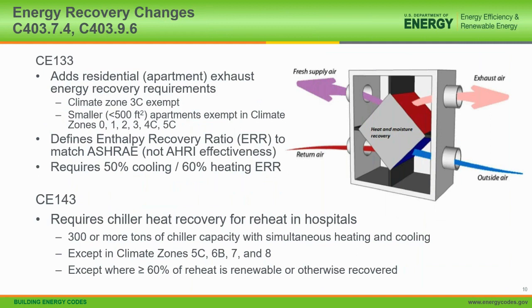Now, rather than just a blanket, more commercially oriented requirement, we have provided a transition where residential or apartment exhaust has more specific energy requirements. Climate zone 3C is exempt. Smaller apartments under 500 square feet are exempt in certain climate zones. They just didn't look to be cost effective there. This was based on an ASHRAE 90.1 proposal that did analyze the cost effectiveness. It provides a new definition for enthalpy recovery ratio that matches the ASHRAE definition.